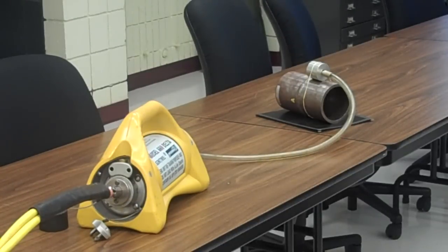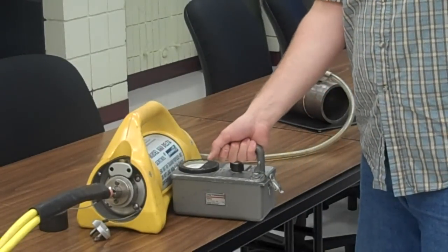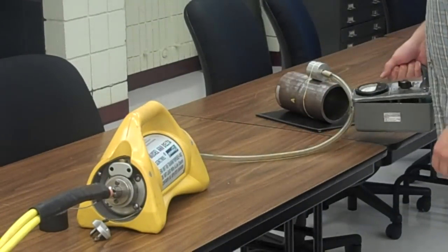Gamma-ray camera's sitting here. Now granted, I know if we were doing this all proper and everything, we'd have our survey meters and everything. So we'll get our survey meter, looking at this thing, making sure we've got it all set up here. We would take our survey meter in here and we would measure right beside of this camera, down the guide tube here to make sure there was no radiation coming out, or at least not at a harmful level.